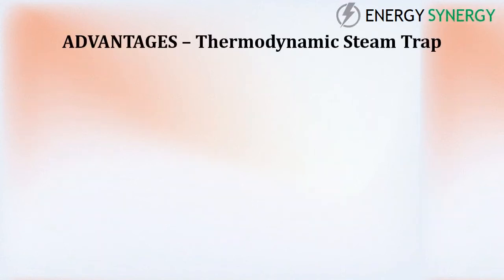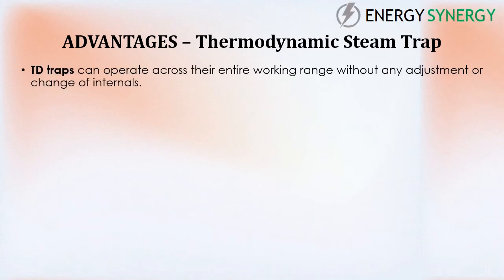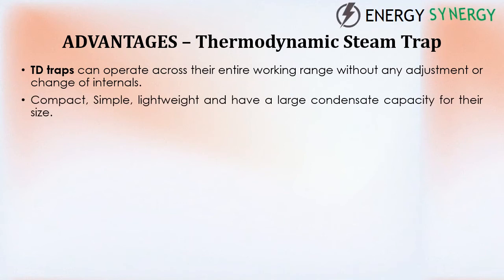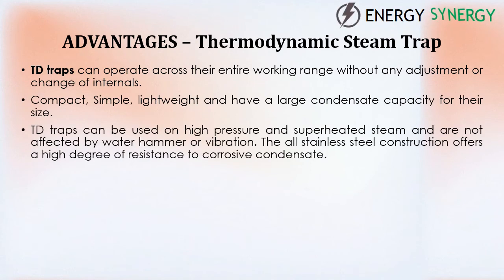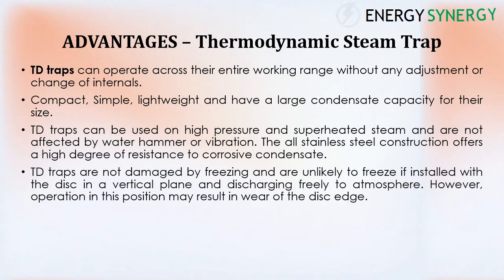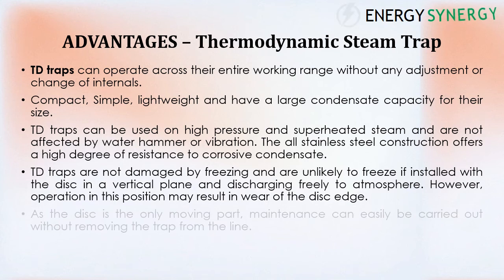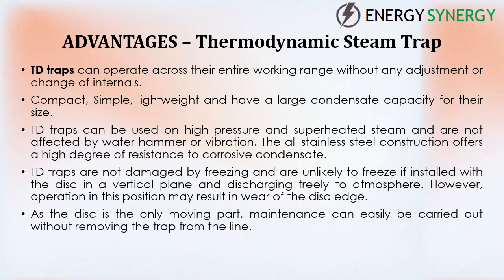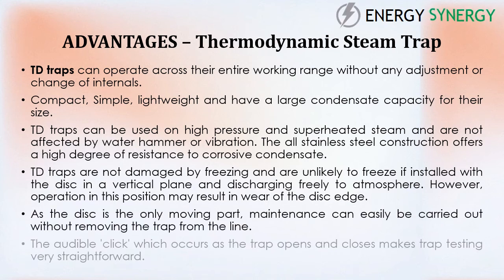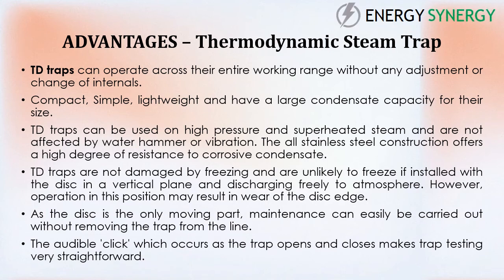Advantages of thermodynamic steam traps: (1) TD traps can operate across their entire working range without any adjustment or change of internals. (2) They are compact, simple, lightweight, and have a large condensate capacity for their size. (3) TD traps can be used on high pressure and superheated steam and are not affected by water hammer or vibration.